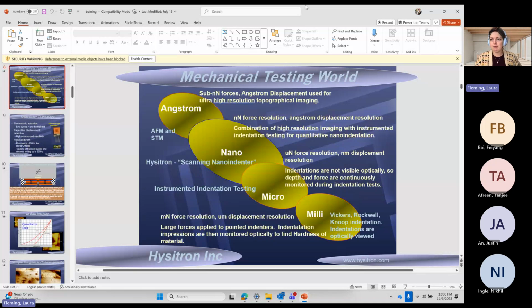There's often a question of where we fall in material testing. On one end of the spectrum, you've got milli indenters, which require large force resolution and large displacement resolution, meaning you're not going to get as fine detail as you would with smaller ones. Vickers requires you to optically see the indent after you've done it so that you can measure it to make those calculations for hardness and modulus. One step up from that is micro, which has micronewton force resolution and nanometer displacement resolution, and that means we don't have to optically resolve the indent in order to make those measurements.